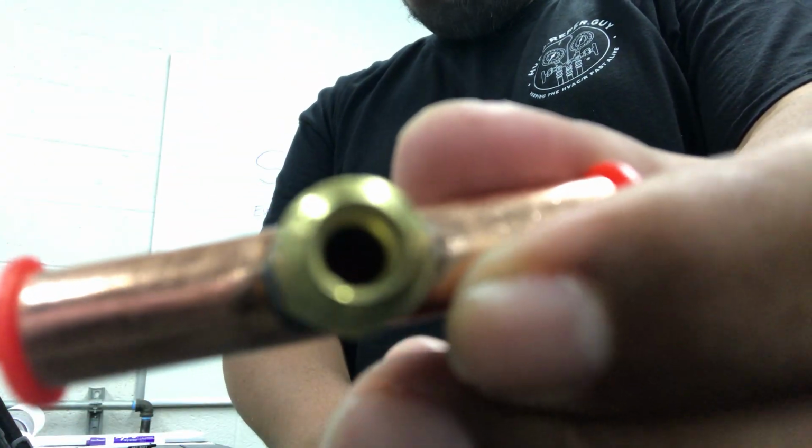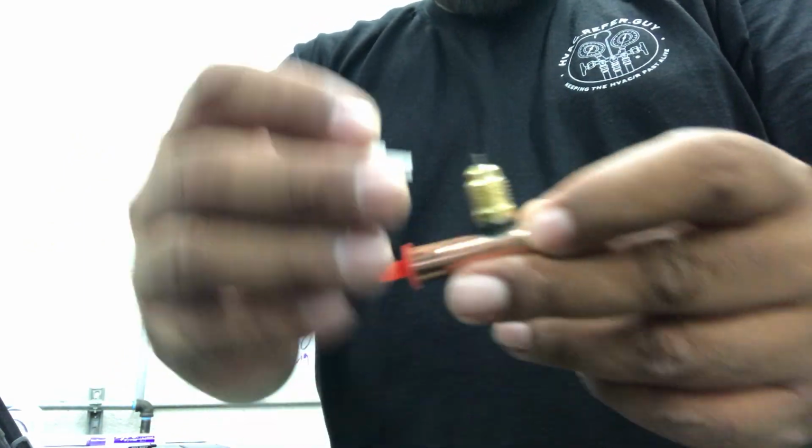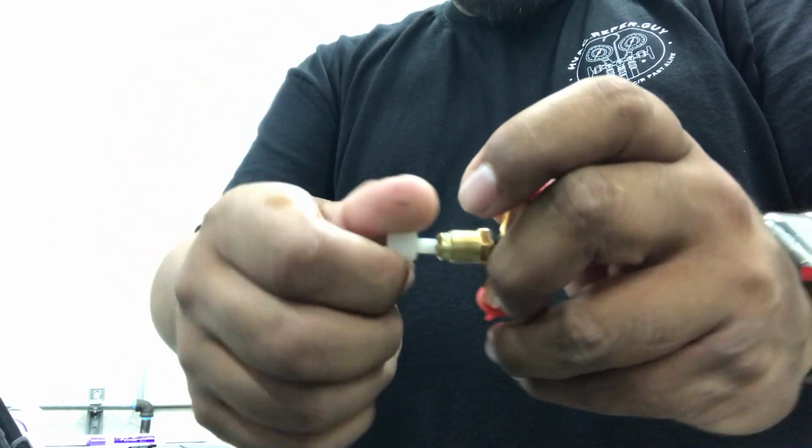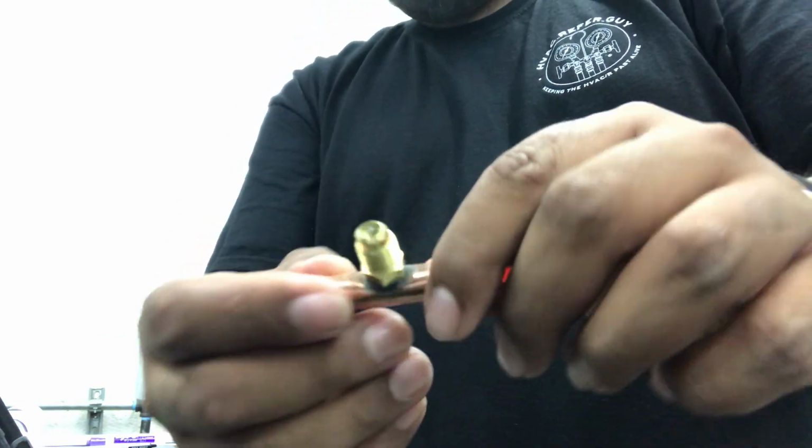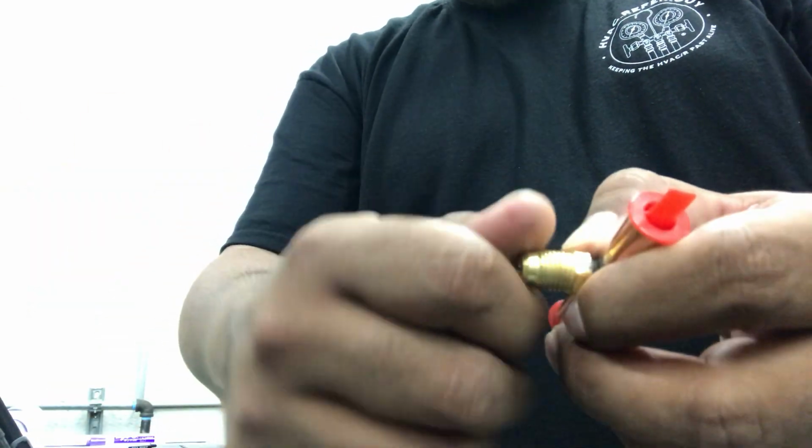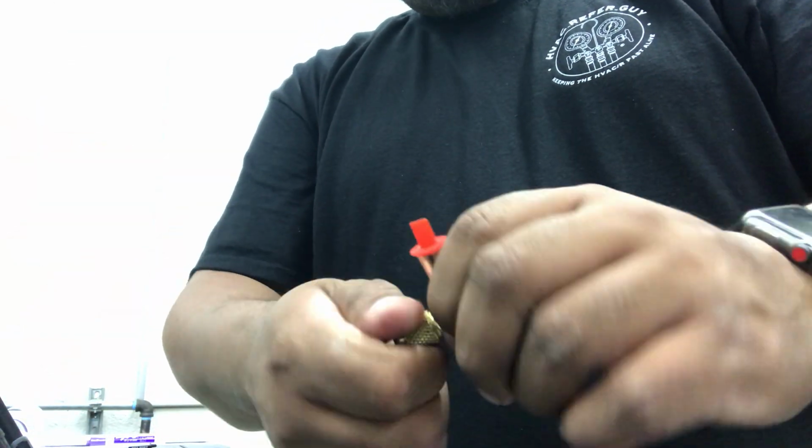So again, that's your actual valve body there. You can see there's nothing in there. All you do is put that little core in there. You grab your tool, and that little core goes here, and we just make it snug. You don't want to Hercules this stuff because you'll damage it. And there you go, it's in there now. Then you just get your hose, screw it on here, and the pressure will shoot out and do its thing. And you just put your cap back on. She's good to go.